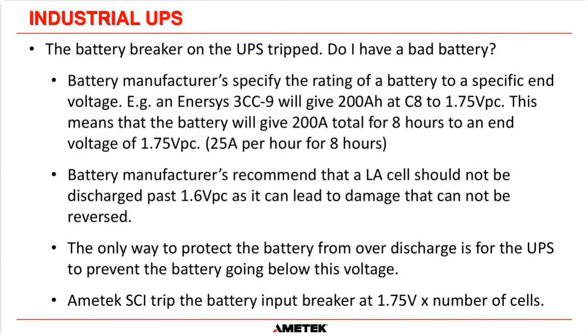The next one, the battery breaker on my UPS tripped. Do I have a bad battery? Maybe. It could be that you have a bad battery, but in most situations, it might not be, because remember what I said earlier about UPS manufacturers protecting the battery? Well, battery manufacturers specify the rating of a battery to a specific end voltage, and the industry standard for industrial UPSs is 1.75 volts per cell. So an example here is for an Enersys 3CC-9 battery, it will give you 200 ampere hours at the C8 rating. And what that means is you'll get 200 amps total for 8 hours. 25 amps basically per hour for 8 hours.